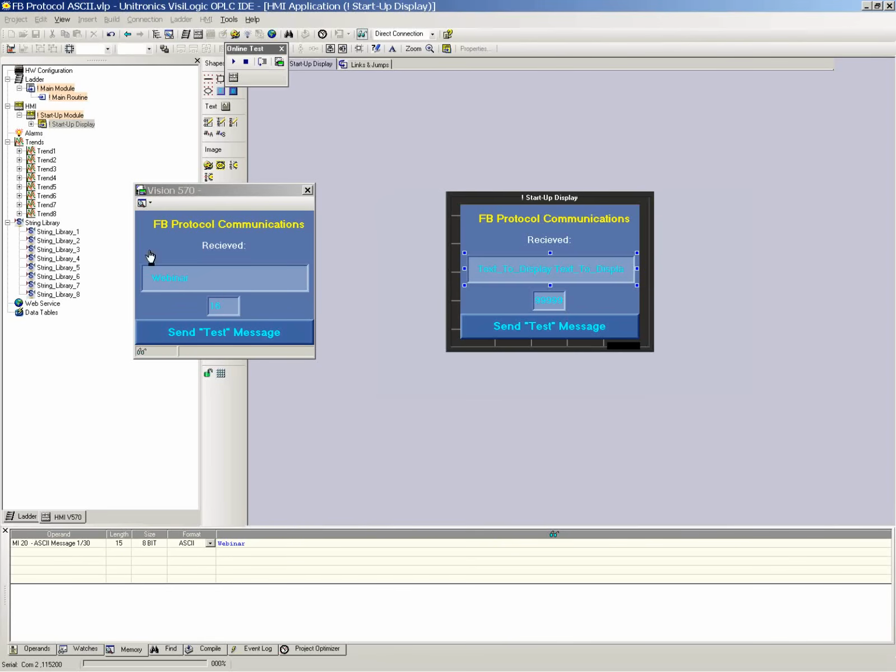One last thing that I can't really show you on my controller because information mode is not supported inside of remote access. However, if you're following along right now with a controller, if you have one on your desk, say, and you know how to enter information mode, you hold your finger down on the screen for 4 seconds as the default time. It will ask you to enter an info mode password. Default password is just 1111, so 4 number ones. Inside information mode, there'll be a tab for serial. And then inside of serial, you'll see on the bottom right-hand side, there will be a tab for monitor.